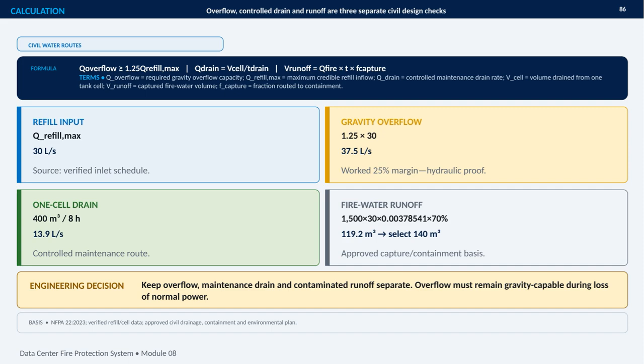For a one-cell maintenance drain, the calculation is 400 cubic meters divided by 8 hours, resulting in approximately 13.9 liters per second. That is a controlled discharge route, not an emergency overflow path. The fire water runoff calculation estimates 119.2 cubic meters from the stated fire flow, duration, and capture fraction, so the selected containment volume is 140 cubic meters. The key engineering decision is to keep these three systems physically and functionally separate, based on NFPA 22, verified refill and cell data, and the approved drainage, containment, and environmental plan.